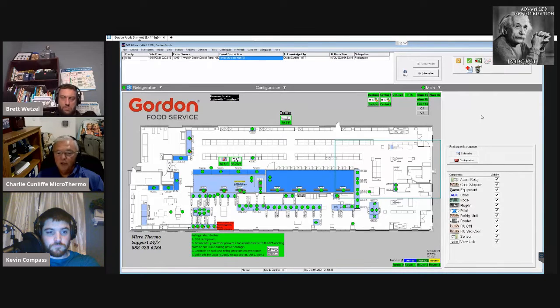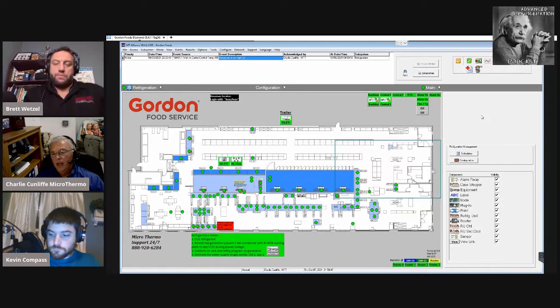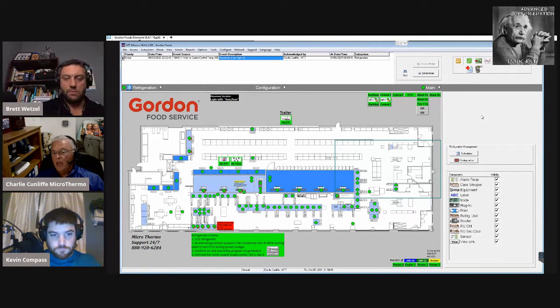Back pressure, head pressure, gas cooler, outside ambient, or whatnot - there are certain things that have to be home run, hardwired, landed to that MT700 that's controlling the rack or the gas cooler, because we don't want even a half second delay in that information being available to the node. Other than that, you can broadcast.